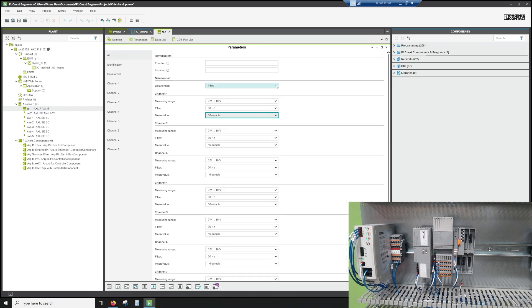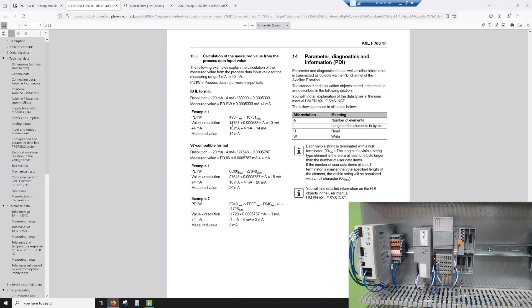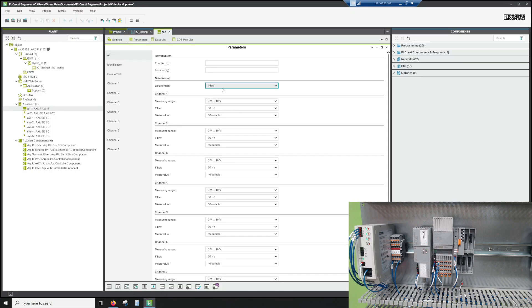There are two data formats: inline and S7 compatible. Looking at the data sheet, in the inline format it's 30,000 counts for the whole scale, and in the S7 compatible format it's 27,648. We're going to leave it in the inline format.